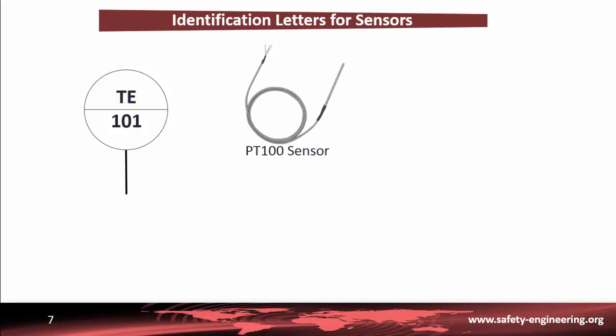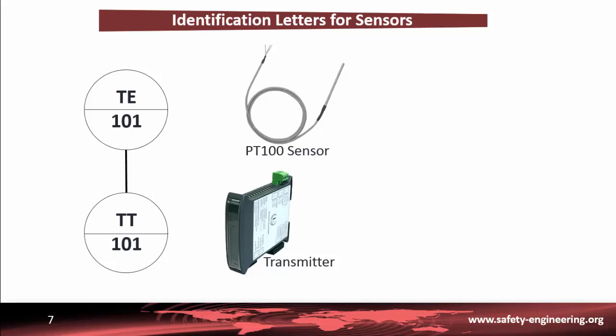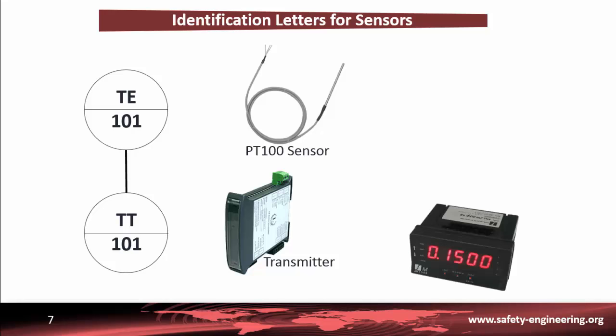If you want to indicate that the sensor is a sensor-transmitter, you put the letter T after the first letter in the second or third position. A transmitter is a device that converts a reading from a sensor or transducer into a standard signal — in general a 4 to 20 mA current loop. In a control loop, an elementary sensor must be connected to a transmitter. Sometimes operators need to check a measurement directly in the process. An indicator makes the reading possible — it is a device readable by humans that displays information about the process.